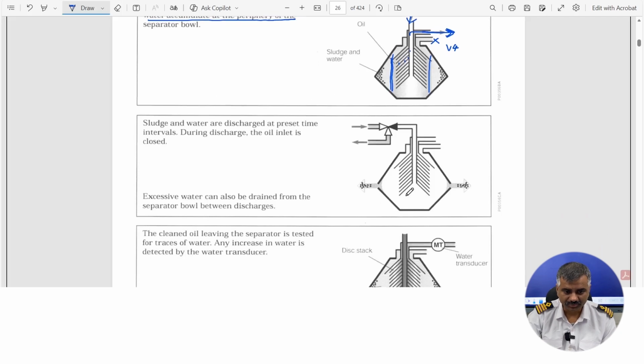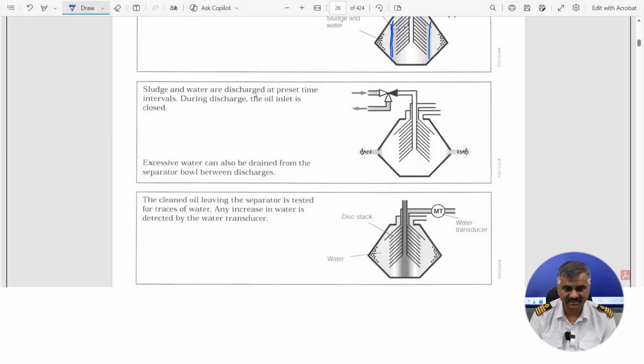Next, sludge and water are discharged at preset time intervals. During the discharge, the oil inlet is closed, the same as happens in the Mitsubishi also. So this is the oil in, and when there is a discharge time, we will discuss the discharge interval as per the timer. Maybe it is 120 minutes or 60 minutes, as we have set the discharge interval. The bowl will open and the sludge will be discharged out, and at that time the oil feed is in the recirculation line.